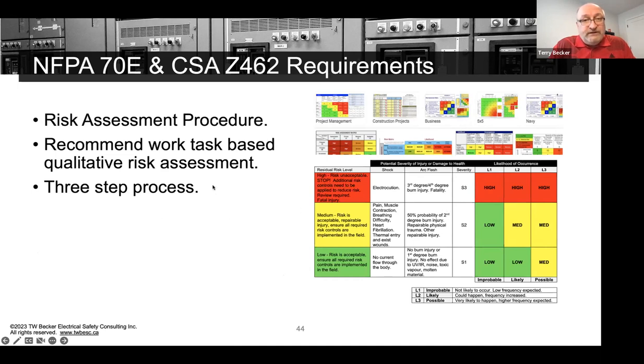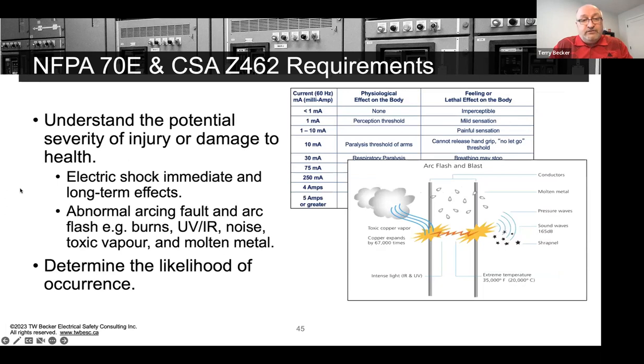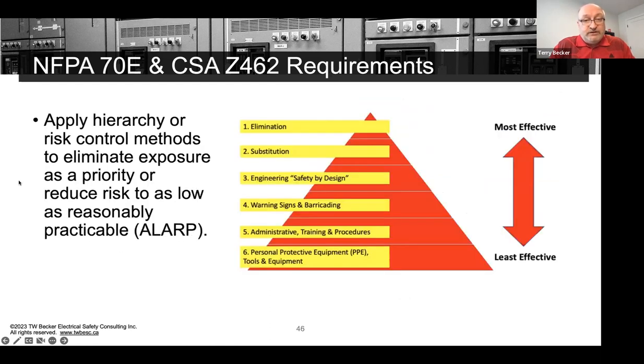I recommend a qualitative work task-based risk assessment, and it's 3 steps. Work task hazard identification, electrical hazard identification, analyze potential severity of injury, damage to health and likelihood of occurrence, and then determine the hierarchy of risk controls that you need to deal with the potential effects of electric shock or arc flash, right? So again, that's the simple 3-step risk assessment procedure, and it doesn't have to be overly complicated, but the employer is supposed to complete that against work tasks.